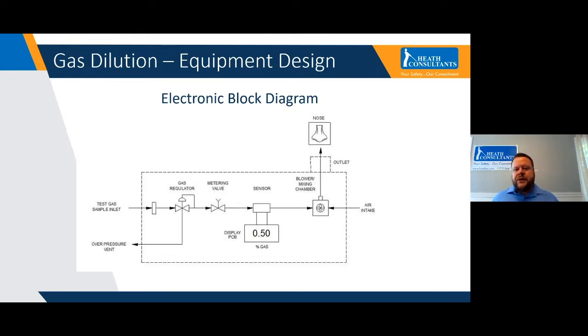Then you open the metering valve and start to introduce that gas into a constant airstream. That gas crosses a mass flow sensor, which gives you a display on your PCB, enters a blowing chamber which mixes the gas and air and blows it out to an outlet port where you'll use your nose to sniff. So that's the basic block diagram of how this instrumentation works.